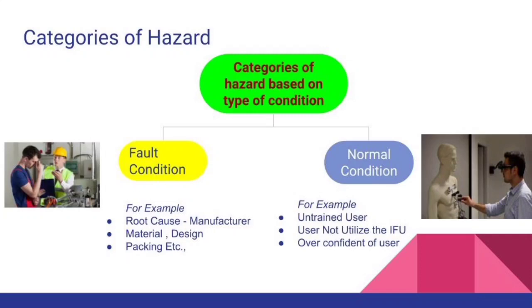The next one is normal condition. The hazards are caused by user error — like an untrained user or untrained professional, user not utilizing the IFU or instruction for use, or overconfidence of the user about the device and operating procedure, and so on.